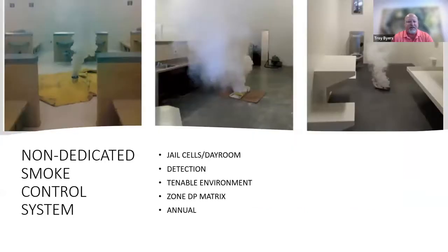Okay, and we can advance there. Now, those were both dedicated systems, right? So now we're going to look at a non-dedicated smoke control system. In this example, we could look at a day room in a jail. We would typically have smoke zones, and the idea here is to contain the smoke within a zone and not allow transfer into other zones. So we typically see a pressurization requirement of differential pressure, zone to zone, of 0.05 to 0.08 inches of water gauge.